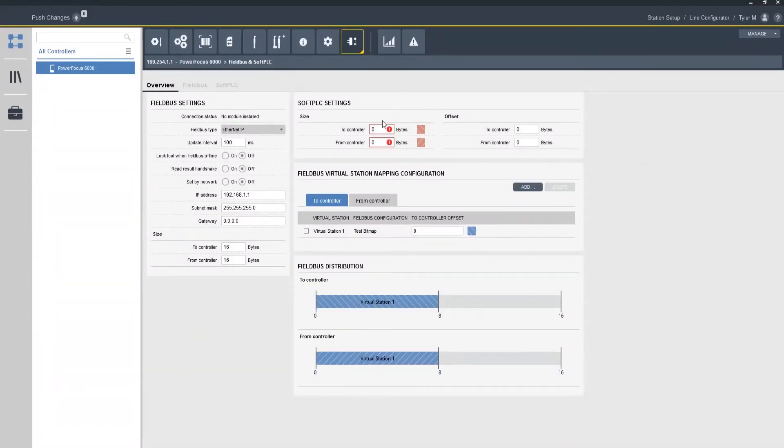So now at this point in time we've programmed our field bus setup. So keep in mind a couple of things about the generic field bus setup. We need to make sure that we're using the correct field bus file type whether it be an EDS file or a GSD file whatever it may be. We want to make sure that we're using the correct one for the Power Focus 6000. And we also want to make sure that we have our generic settings such as update interval set accordingly with the PLC.